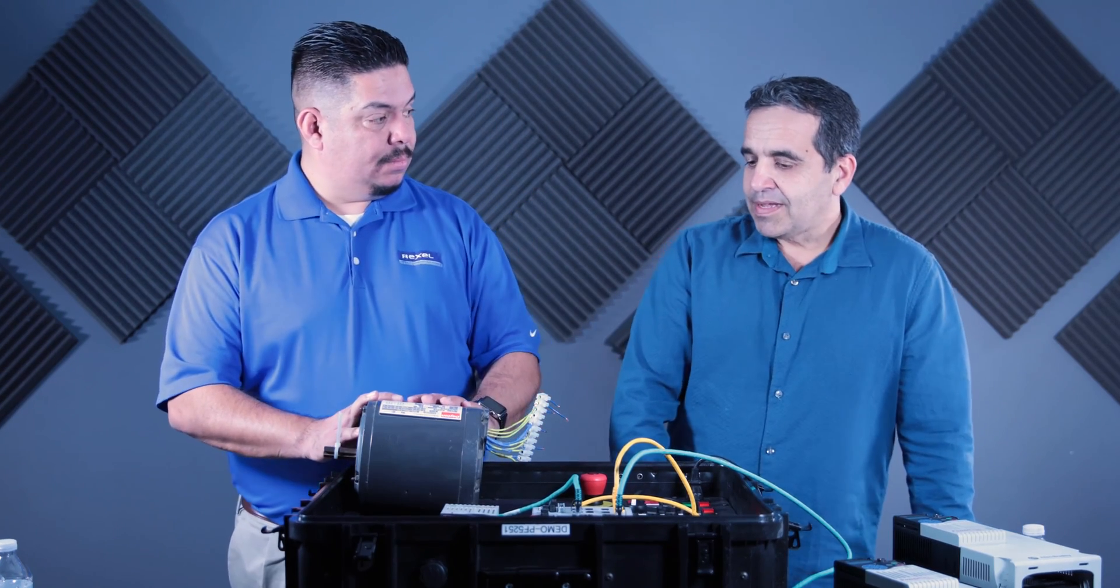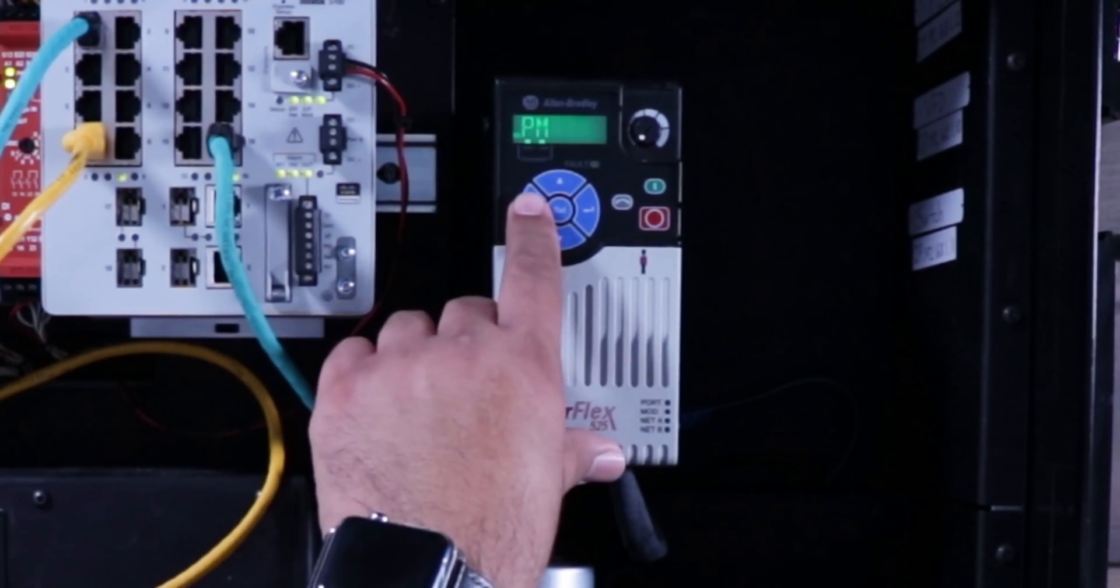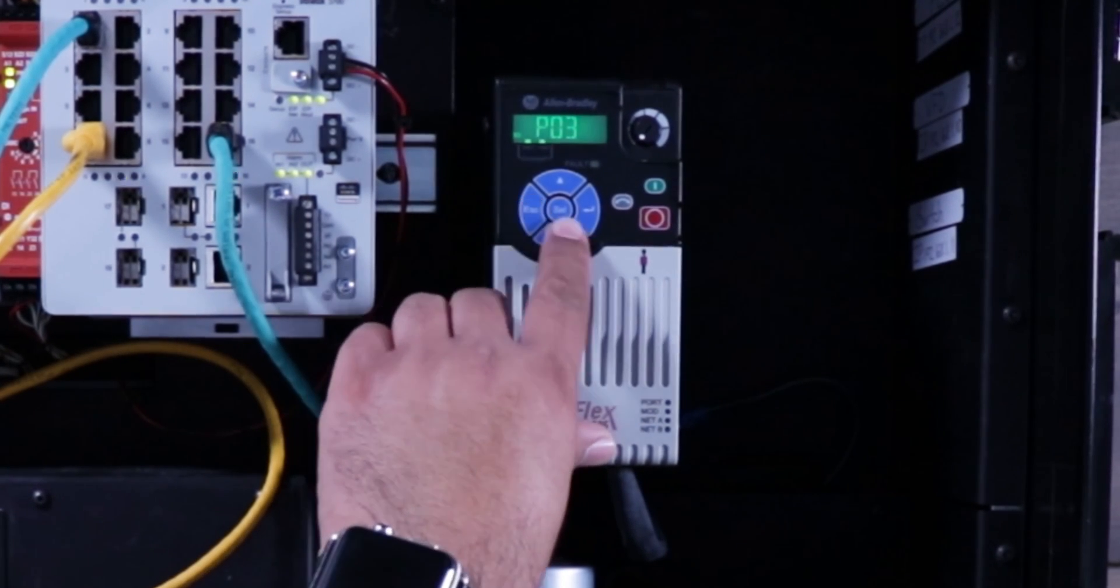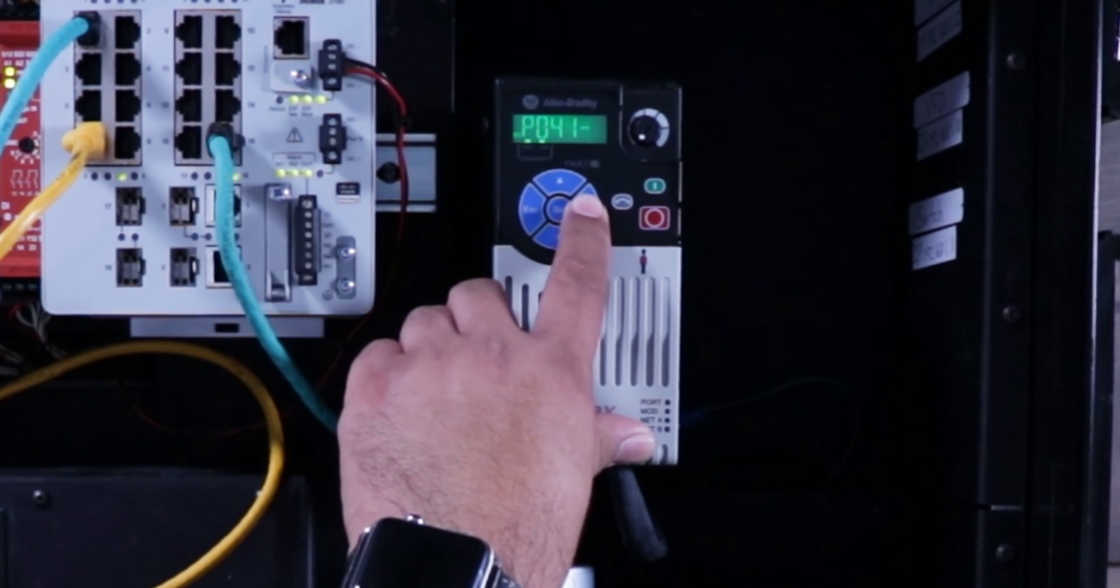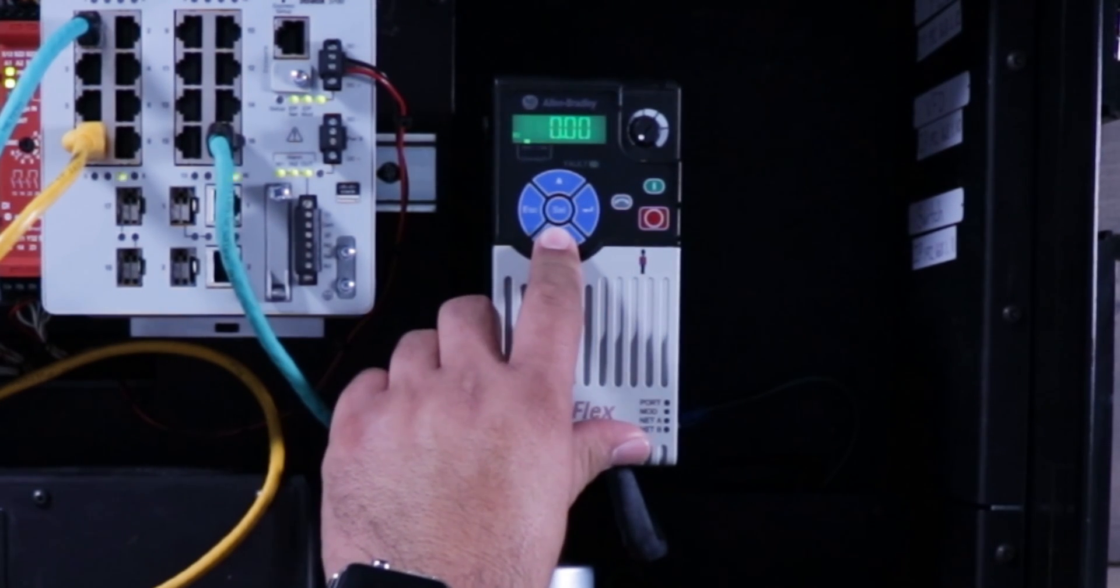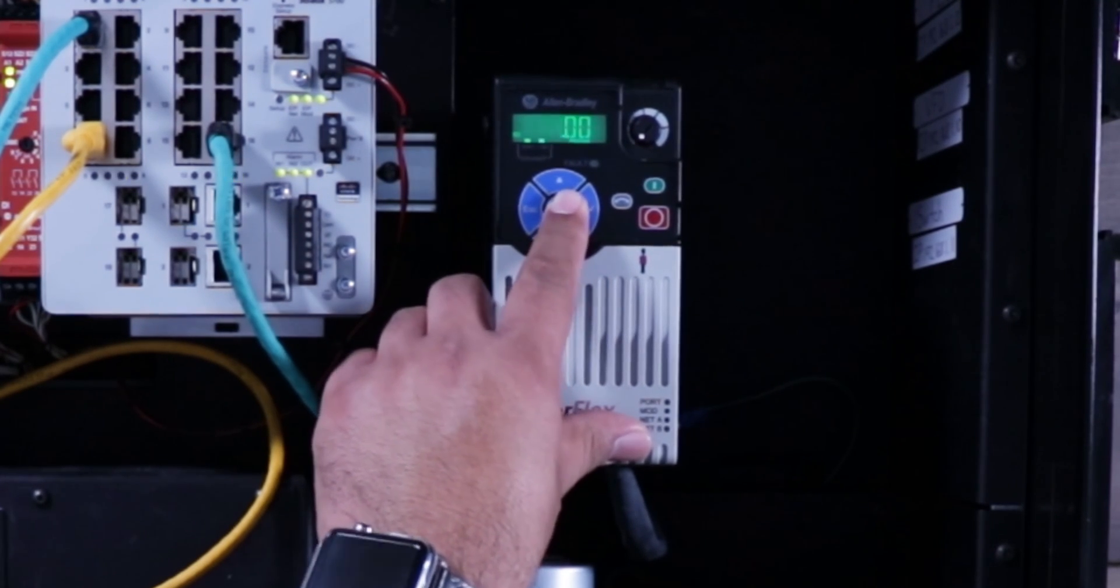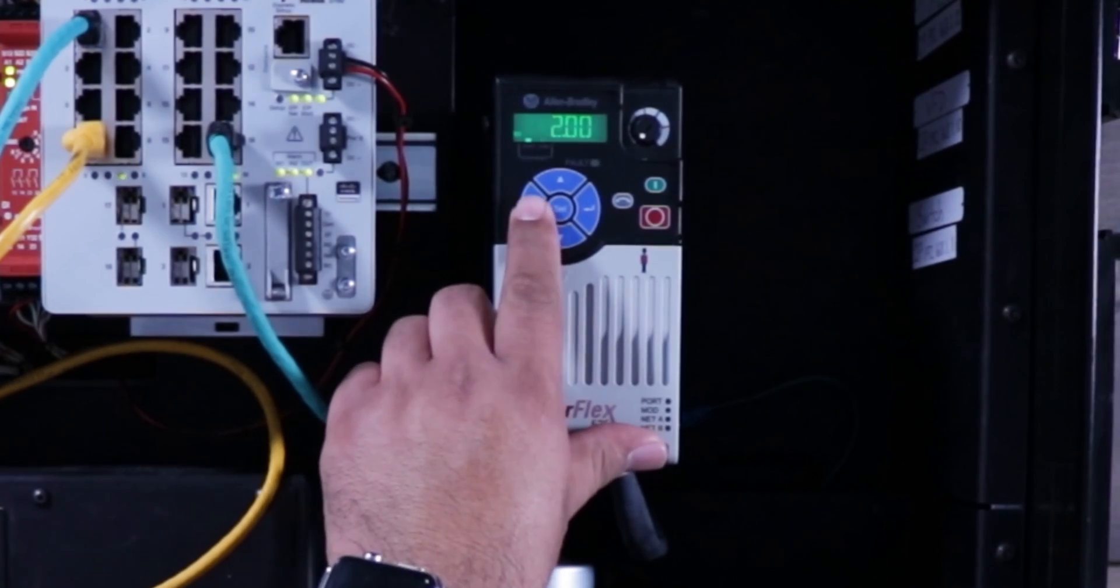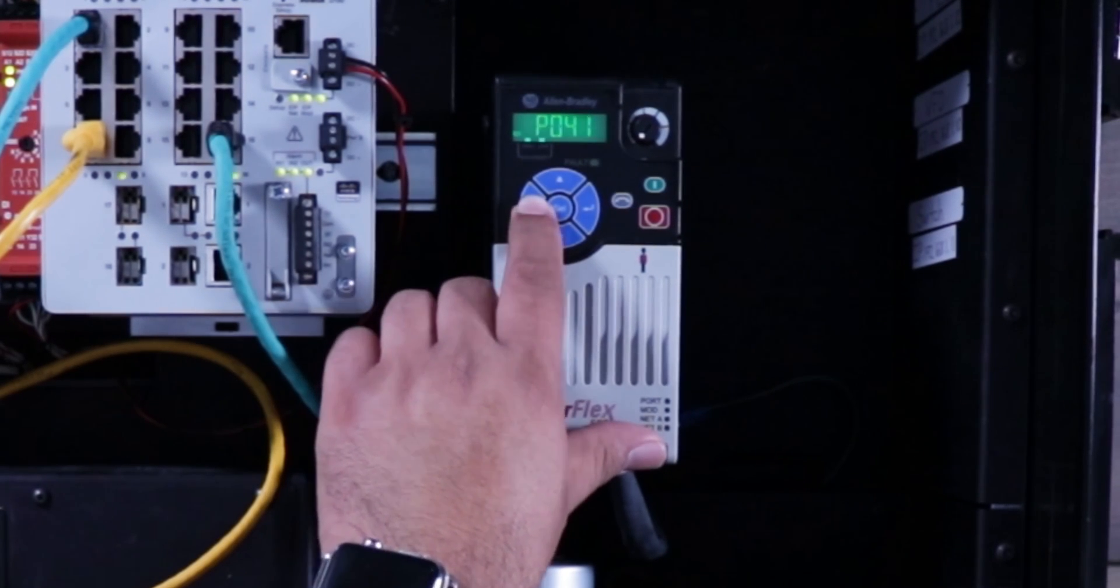Now we probably need to think about the accel time. So the start time, the accel time, which is P41, this is how long it's going to take the motor to get up to speed. So you can set it anywhere from 0 to 600 seconds. So we'll go ahead and set this one to 2 seconds. There we go. And the default was 10 before we started messing around with it. So we'll set the acceleration time to 2 seconds. And that's how fast it'll get up to frequency, that's how long it'll take.